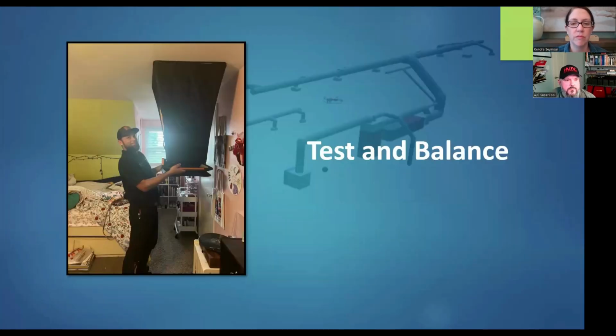Okay, so test and balance. We need to make sure the ductwork is actually delivering the air where it needs to go. Manual J tells me this particular room needs X amount of BTUs - we need to deliver 150 cubic feet of air per minute. We have an 8-inch duct, and we need to confirm with the flow hood that this duct is actually delivering the airflow needed to that room.